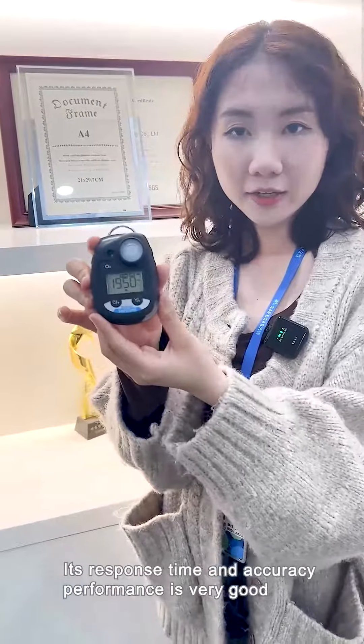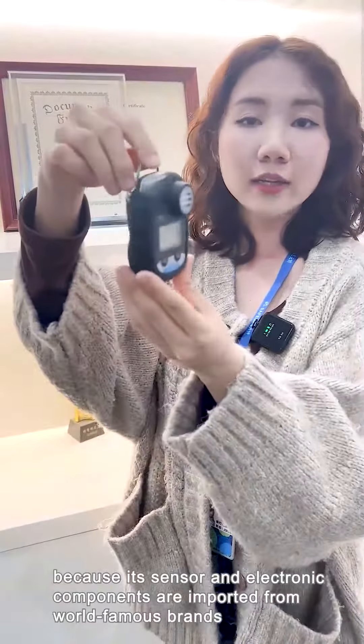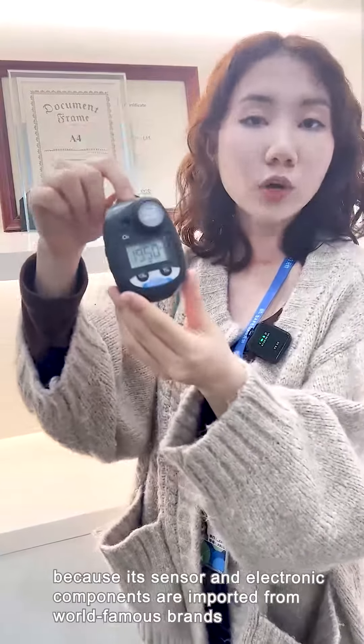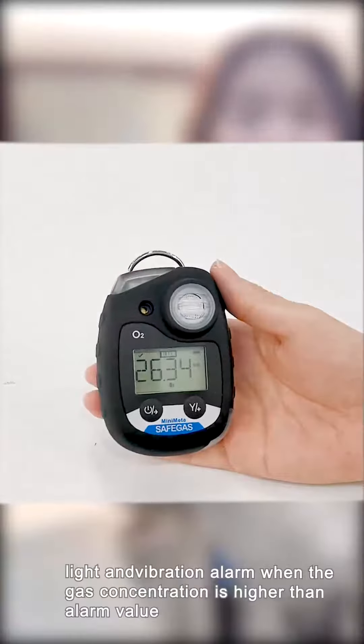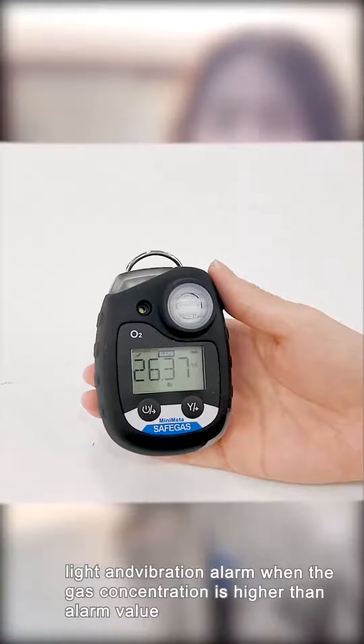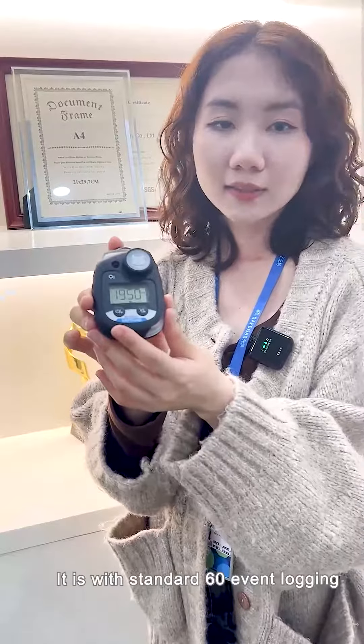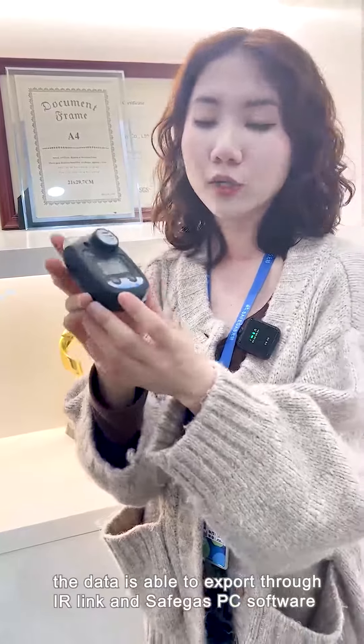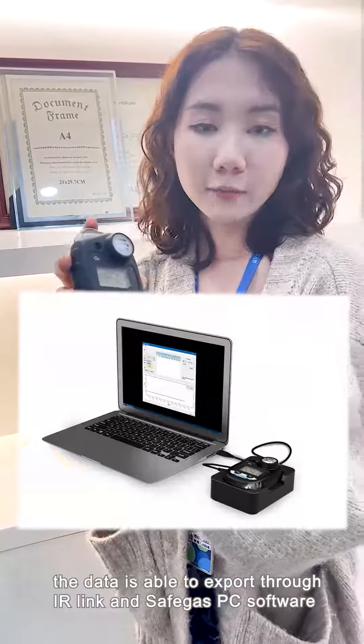Its response time and accurate performance are very good because its sensor and electronic components are imported from world-famous brands. This model features sound, light, and vibration alarms when the gas concentration is higher than the alarm value. It includes standard 60-event logging, and data can be exported through IR, LINK, and Safegas PC software.